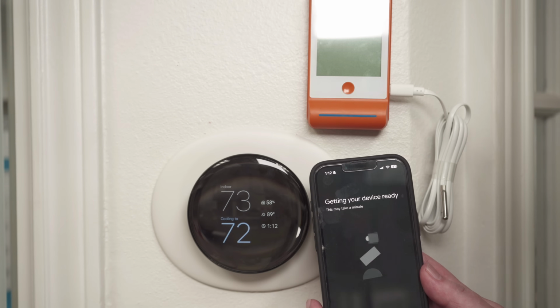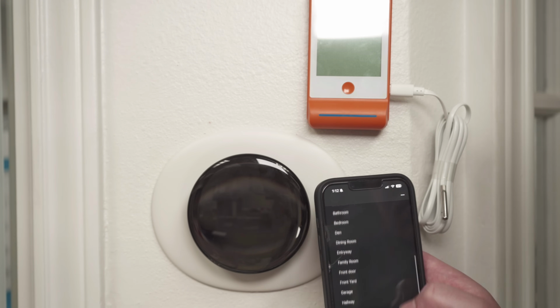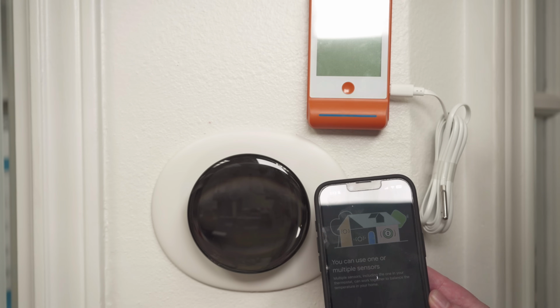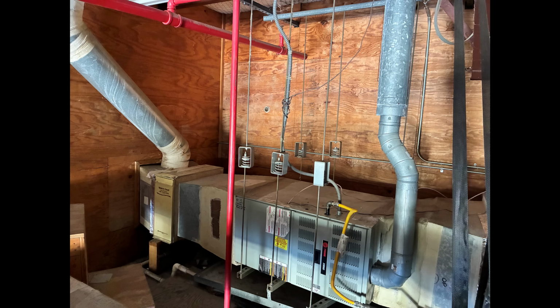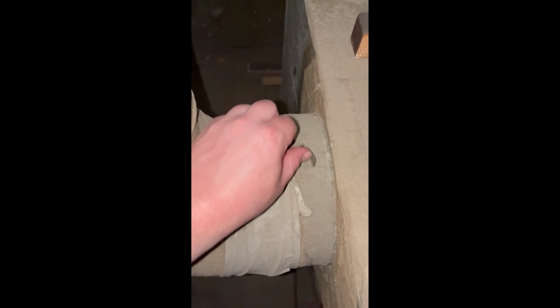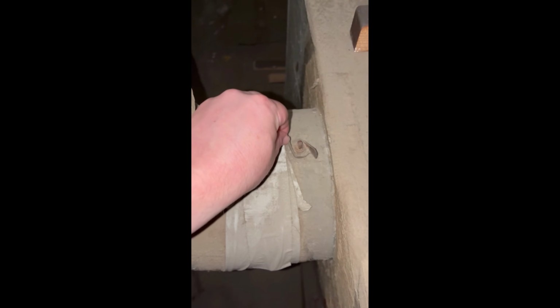There are a lot of things that could cause high humidity. Since this is a commercial building, my first thought is something going on with the fresh air. This pipe is the fresh air intake, pulling outdoor air into the unit. I should be able to tighten the damper to reduce fresh air coming in. When I crawled to the front unit, I found the damper was completely broken, so we're getting 80% humidity outdoor air dumped into the unit, driving up the humidity.